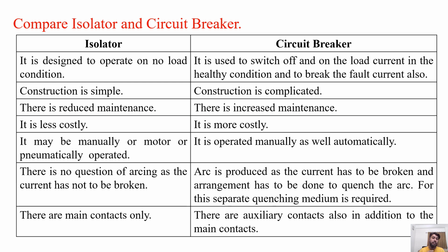In case of an isolator, there is no question of arcing as the current does not have to be broken. It operates on no load condition. Whereas in case of a circuit breaker, an arc is always produced as the current has to be broken, or the contacts are separated when the circuit is on load condition. So the arrangement has to be made to quench the arc produced. For this, a separate quenching medium is required. There are main contacts only in case of an isolator, whereas in case of circuit breakers, there are main contacts as well as auxiliary contacts. So these are some points for the comparison between isolator and circuit breaker.